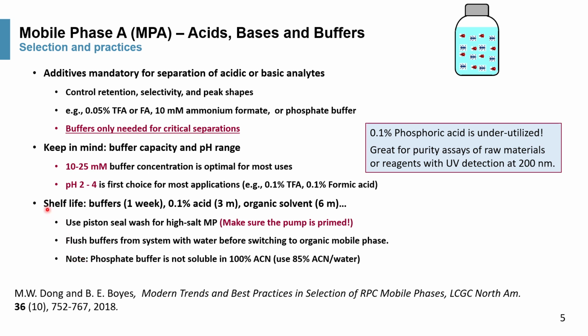Here are some guesstimates for shelf life. It's very difficult to know exactly what the shelf life of these mobile phases is. Using common knowledge, one can guess that for buffer it is probably about a week. If you refrigerate it, you can keep it a little longer. For neutral buffer, it's definitely a little bit on the low side. And always keep it away from sunshine to prevent accelerated algae growth. For a simple acidified mobile phase such as 0.1% TFA in water, a shelf life of 3 months is to be expected. For all organic solvents, at least 6 months. The exception is THF. Once you open a bottle of THF, tetrahydrofuran, you have to throw it out because of the danger of explosion from the peroxide.